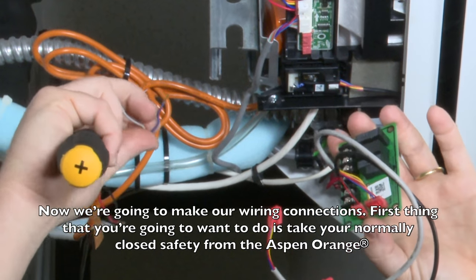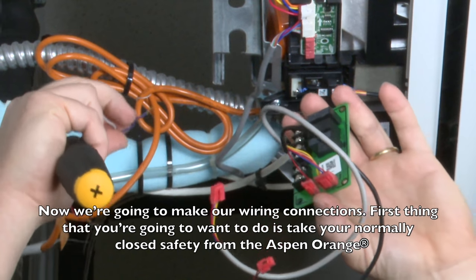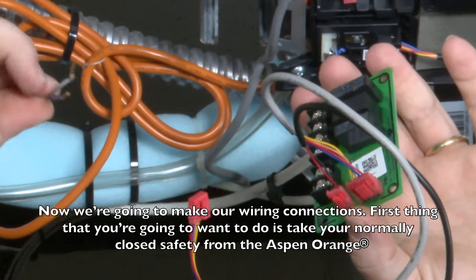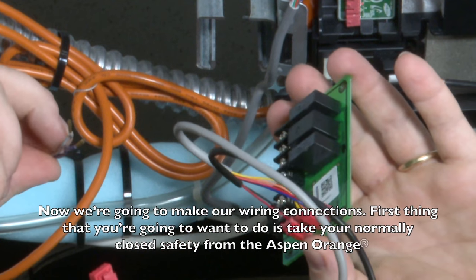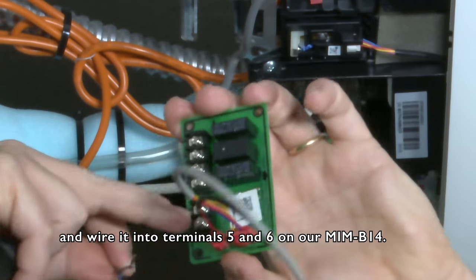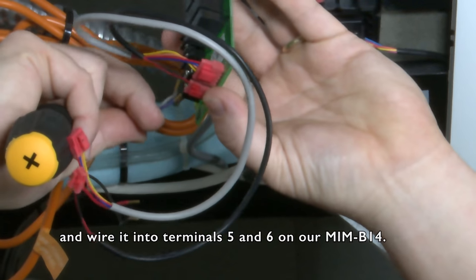Now we're going to make our wiring connections. First thing you're going to want to do is take your normally closed safety from the Aspen orange and wire it into terminals 5 and 6 on our MIM-B14.